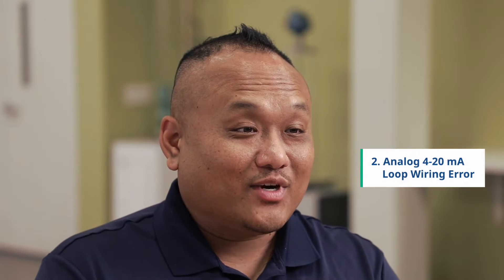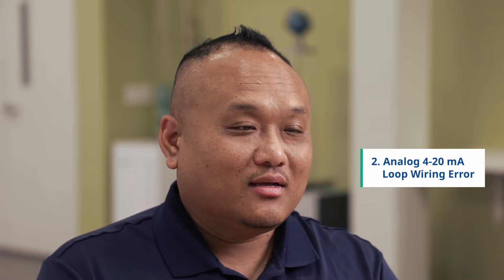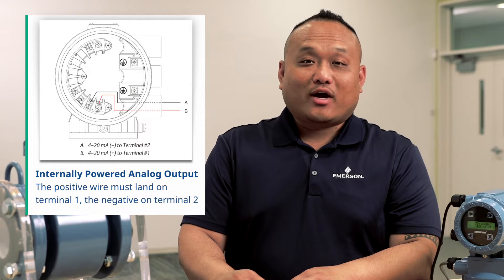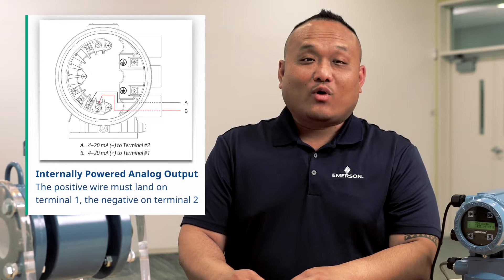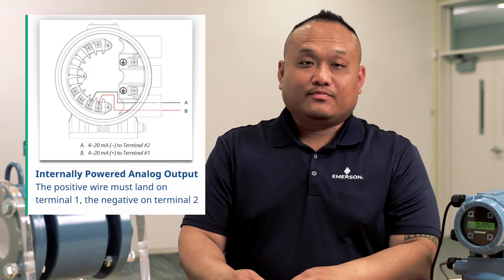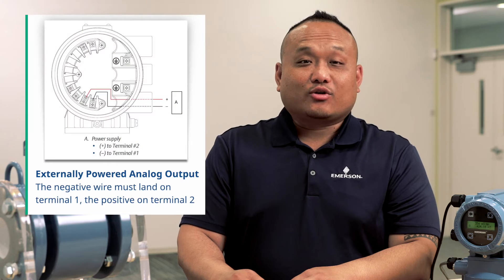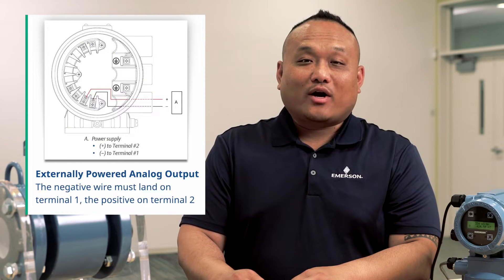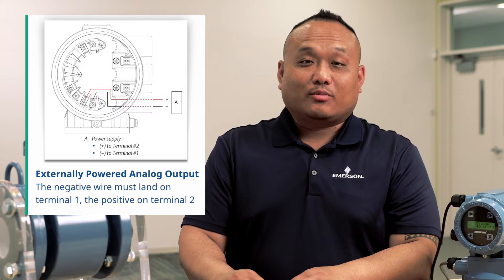Second, verify the analog 4 to 20 milliamp loop wiring. If the transmitter is supplying loop power, the positive wire must land on terminal 1 while the negative wire lands on terminal 2. If there is an external power supply powering the analog output, the negative wire must land on terminal 1.